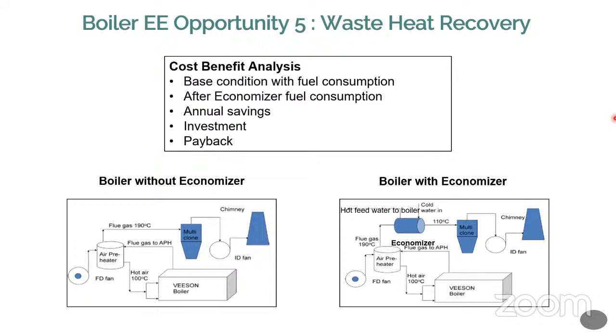The heat available in the flue gas can be taken to the boiler feed water tank, or a small pump will circulate the water through this duct of the flue gas, and the amount of heat taken by the water will be given to the feed water tank.